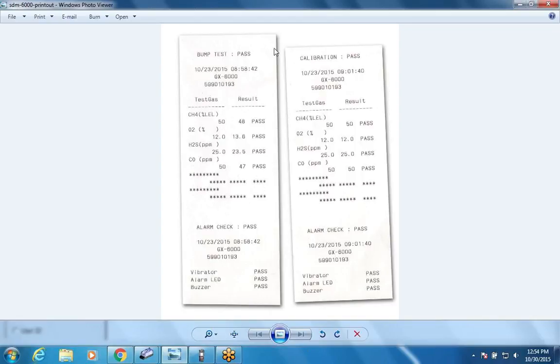So you can see this one's a bump test, and this is a calibration test. It passed. Here's the date and time it was tested, the serial numbers, and the test results. The asterisks are because these two units actually had other sensors in there that we didn't test for that test, so it won't show them. And then it shows you that we did an alarm check and that it passed all three functions.